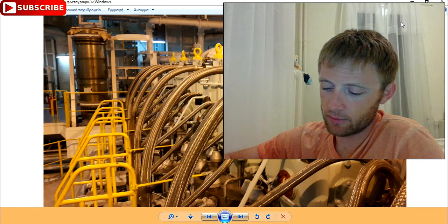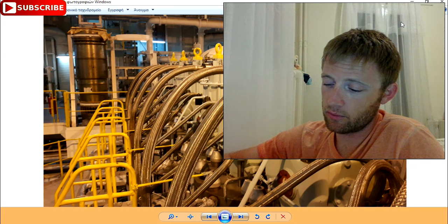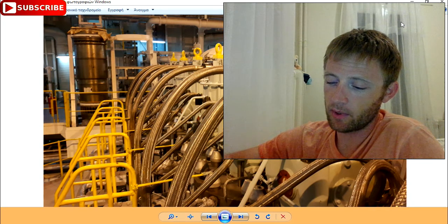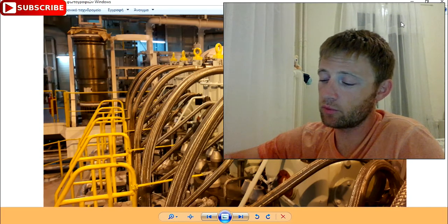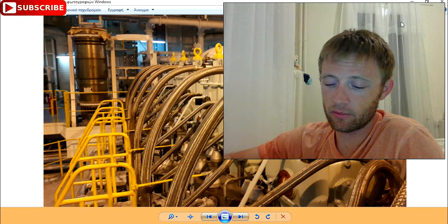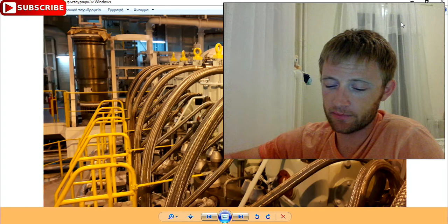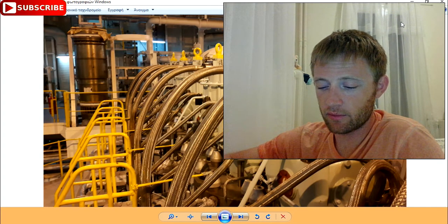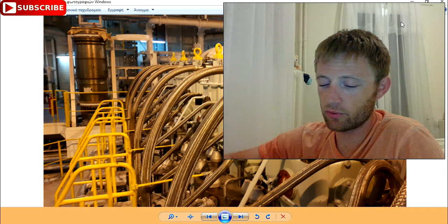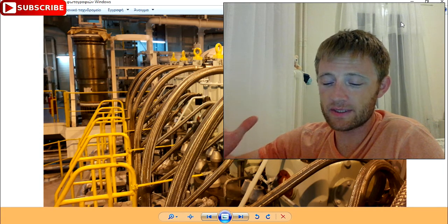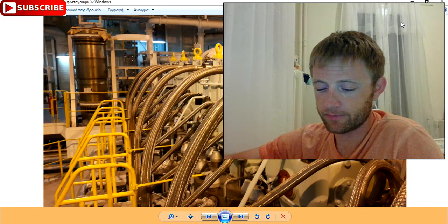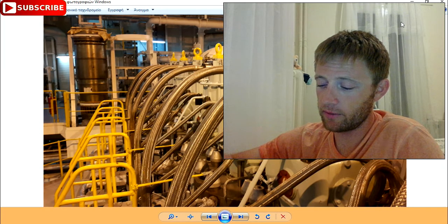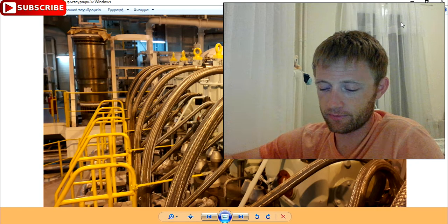Number 17. If you clean the wear sensor, okay, the indication, and you still have the same alarm, we do not operate the system, okay? We look for what is happening inside. Number 18. The wear indication shows what is going on inside the pump, okay? This is the indication of the condition inside. Number 19. Every 6 months we clean this wear indication.